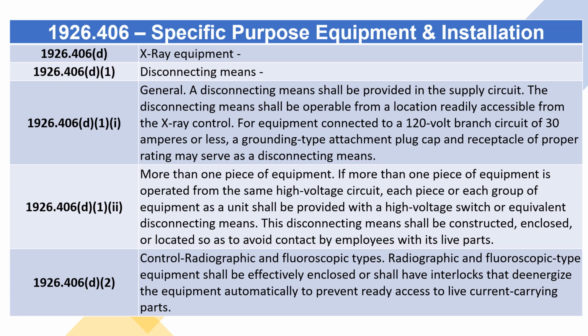1926.406(d) X-ray equipment. 1926.406(d)(1) Disconnecting means. General. A disconnecting means shall be provided in the supply circuit. The disconnecting means shall be operable from a location readily accessible from the X-ray control. For equipment connected to a 120-volt branch circuit of 30 amperes or less, a grounding type attachment plug cap and receptacle of proper rating may serve as a disconnecting means.